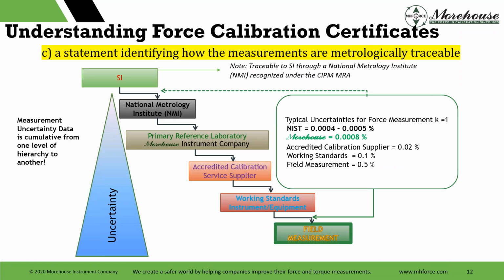Here we have what we're talking about. This is like a pyramid where the measurement uncertainty data is cumulative from one level of the hierarchy to the other. So when measuring force, the load cell should be calibrated using measurement standards traceable to the SI through a National Metrology Institute, recognized under the CIPM MRA. This recognition is necessary as some NMIs cannot provide traceability.